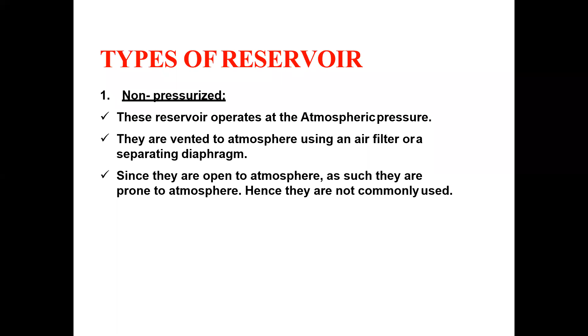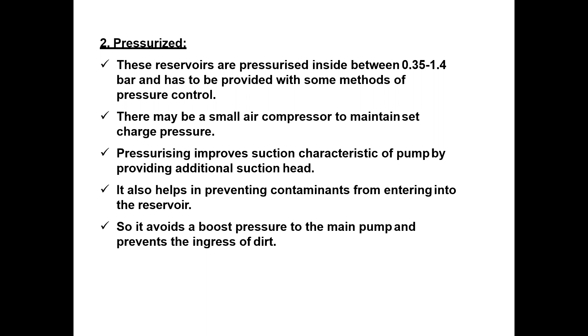And again, the second type is the pressurized reservoir. These reservoirs are pressurized inside between 0.35 to 1.4 bar and have to be provided with some method of pressure control. There may be a small air compressor to maintain a set charge pressure. Pressurizing improves suction characteristics of the pump by providing additional suction head. It also helps in preventing contaminants from entering the reservoir. So it provides a boost pressure to the main pump and prevents the ingress of dirt.